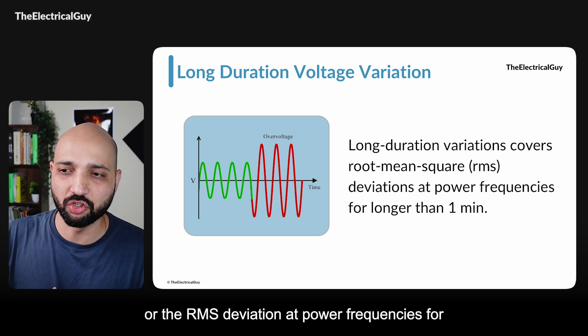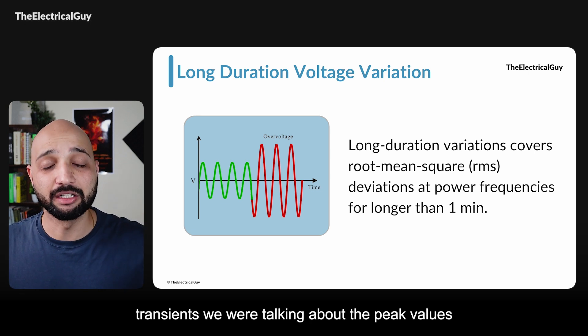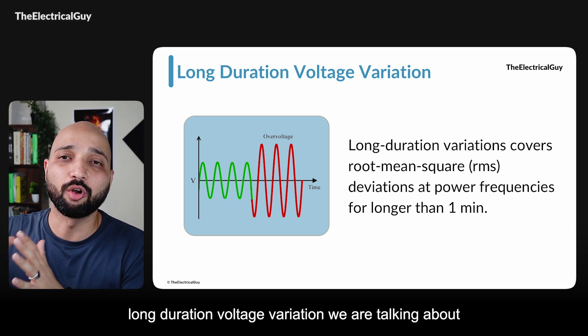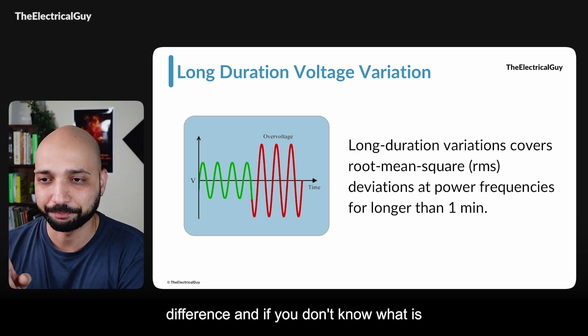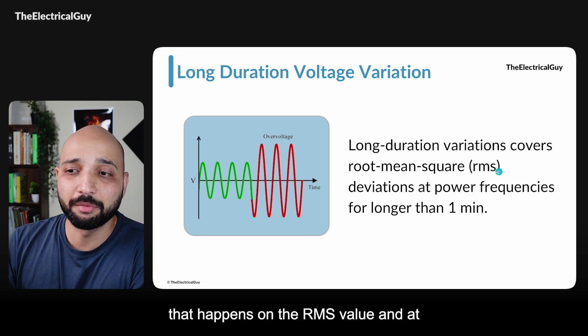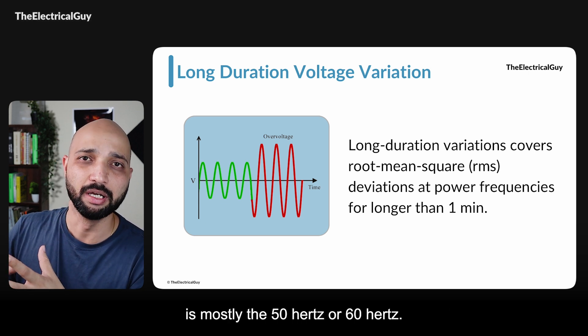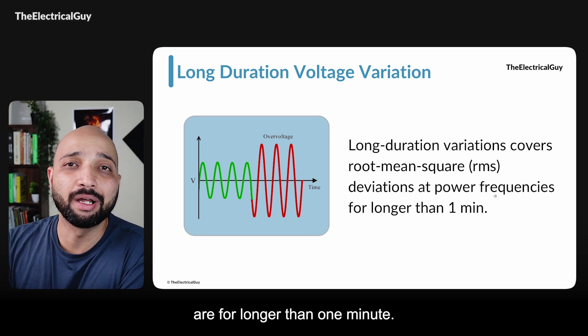Moving on, let's talk about long duration voltage variations. Long duration variations cover RMS deviations at power frequencies for longer than one minute. When we talked about transients we were talking about peak values, but for long duration voltage variation we are talking about RMS values — this difference is very important. Power frequency means the frequency at which we generate, transmit, and distribute electricity, which is mostly 50 Hz or 60 Hz. So we are covering deviations happening at power frequency that last longer than one minute.